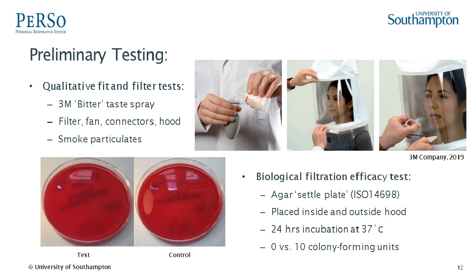Second, we tested the device's filtration efficacy by placing agar plates inside and outside the hood and exposed them to 1 cubic meter of airflow, and then we incubated them at 37 degrees for 24 hours. The plate which was inside the hood, the one on the left, showed no so-called colony-forming units, whereas the control plate showed 10. You might have to zoom in and see through the dust on your monitor, but there are a few small white specks on that right-hand plate.